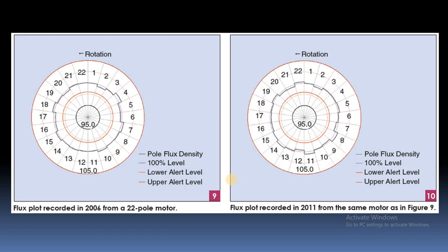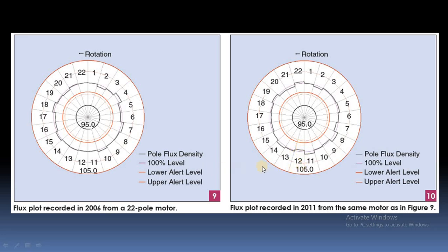Here we can see the rotor flux waveform of a motor having 22 poles. The flux density is plotted, and the inner lines represent 95% and 105% of the average flux as lower and upper limits respectively. All poles are within these limits — no pole is crossing the upper or lower limit — meaning this motor does not have any shorted turns. In this way we can determine which pole has shorted turns using the online technique.